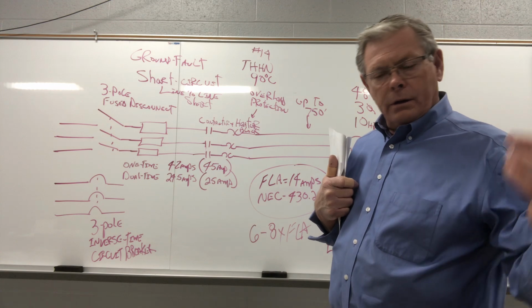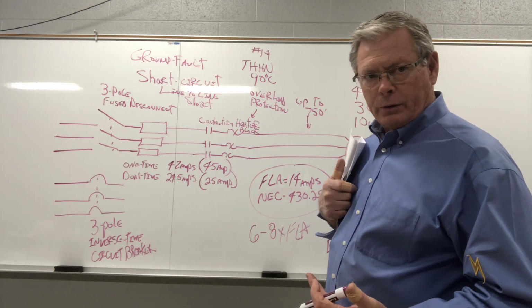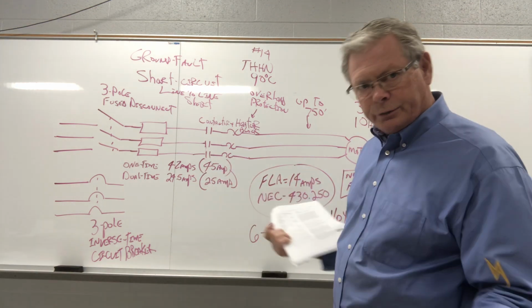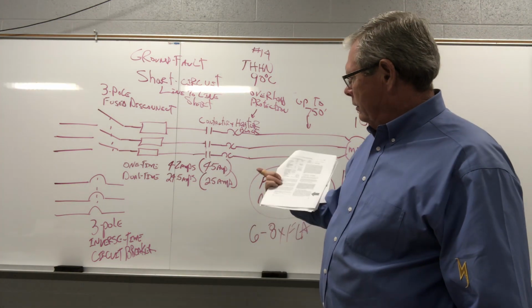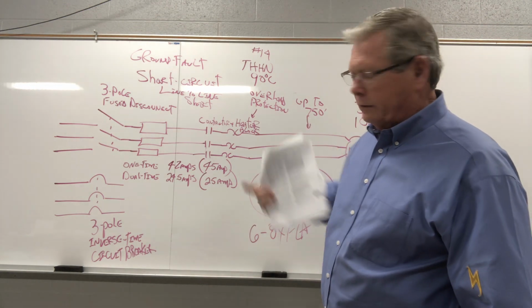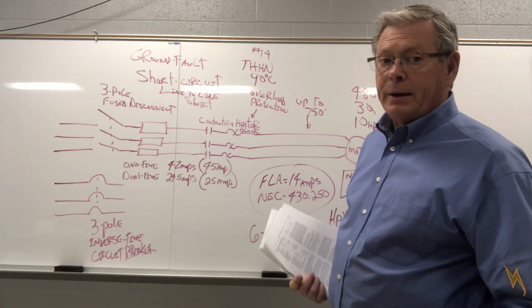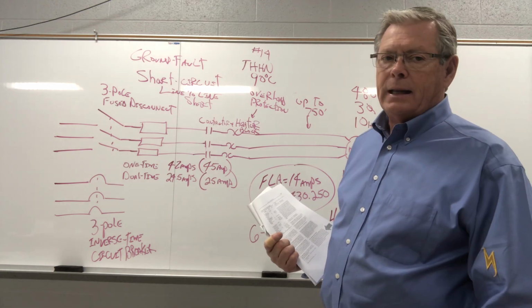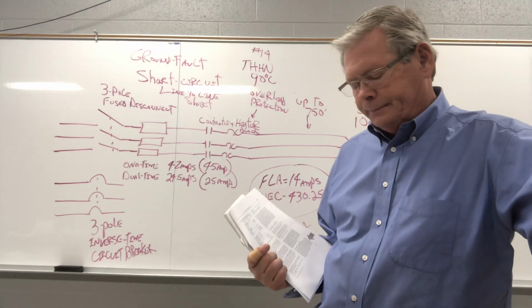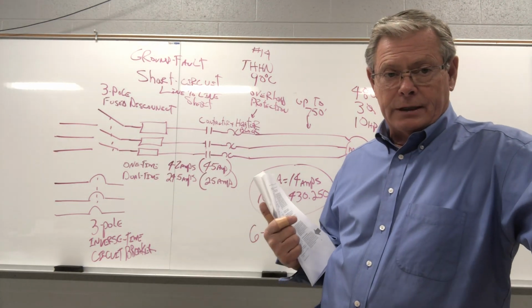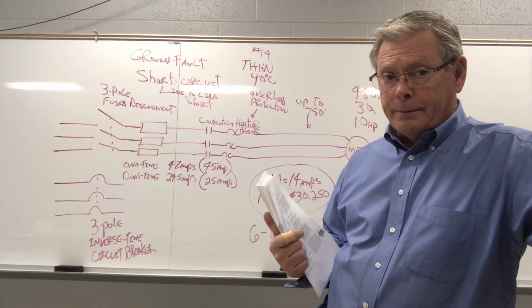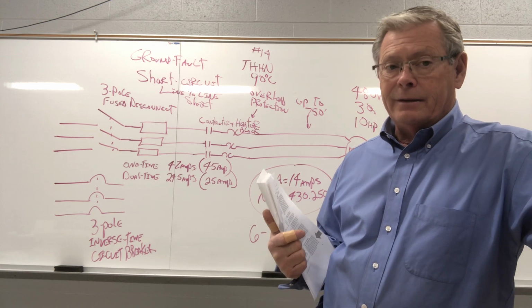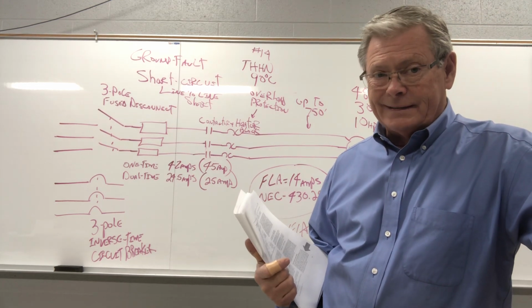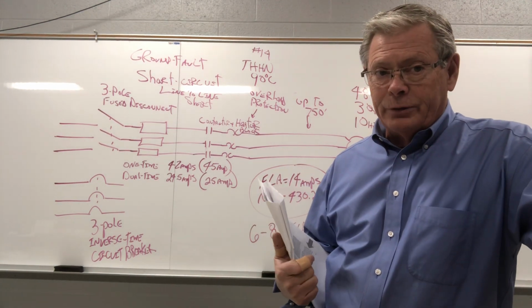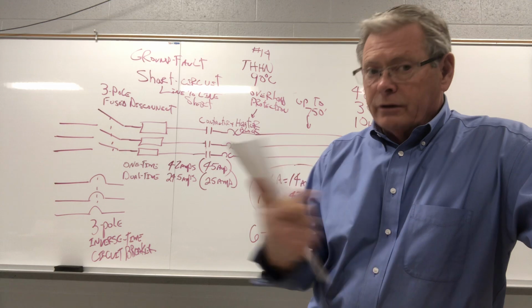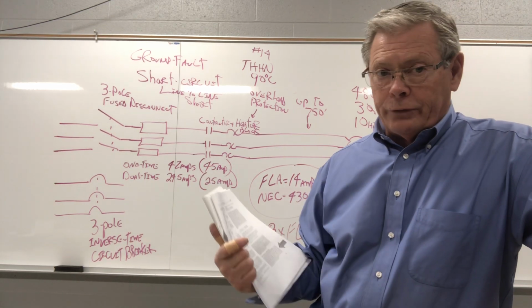So at 2 in the morning, if you need to put fuses in that motor to get it going because it burned up, you changed it out, it blew the fuses because it went to ground, and you don't have any more 25 dual elements, you could do the math, get 45 amp single blow, single element fuses, and put them in there. Now, a footnote. To do this right, you've got 3 fuses, right? You would change all 3 of them out to non-time delay. And then the next morning, or whenever you got the right dual elements in, you put all 3 25 amp dual elements in instead of having 2 of one and 1 of another. So changing all three is the correct way to do it.